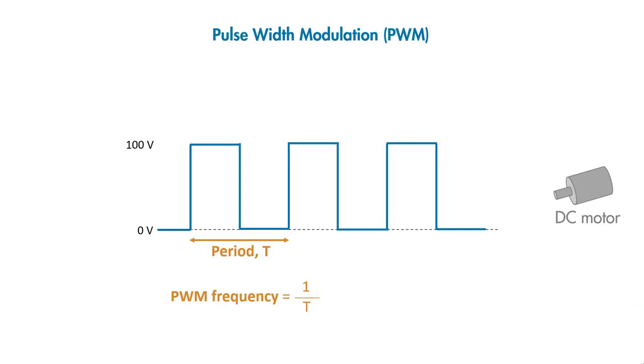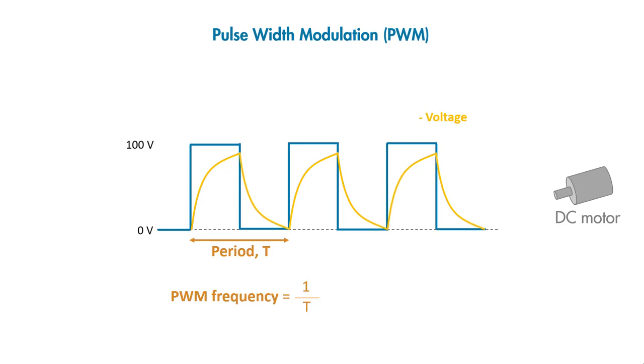If the switching frequency is too low, instead of seeing an averaged voltage, the motor will see a voltage that tries to follow the square wave shape. This will lead to poor tracking of the reference speed, and the motor will keep speeding up and slowing down.